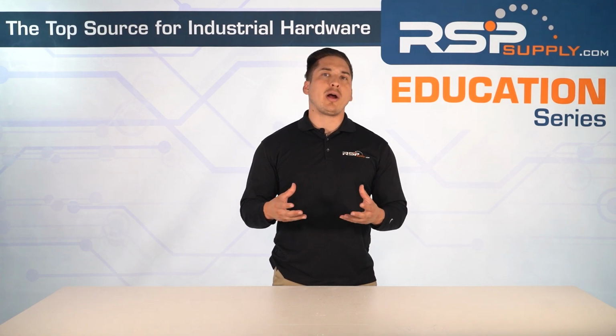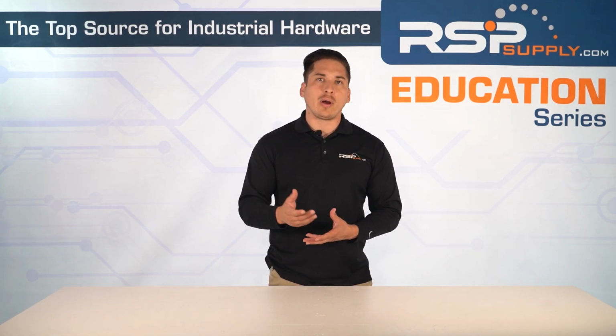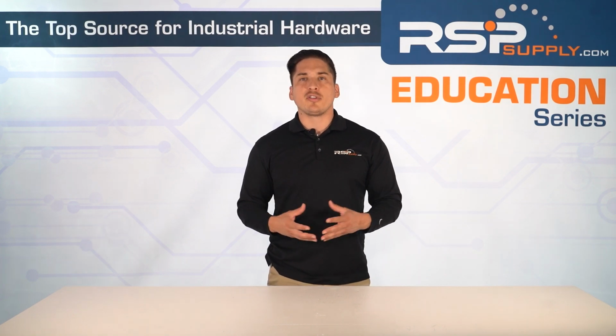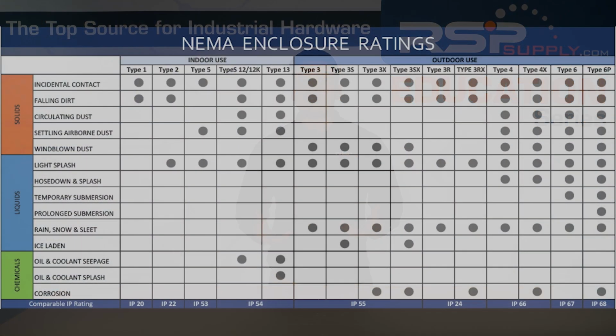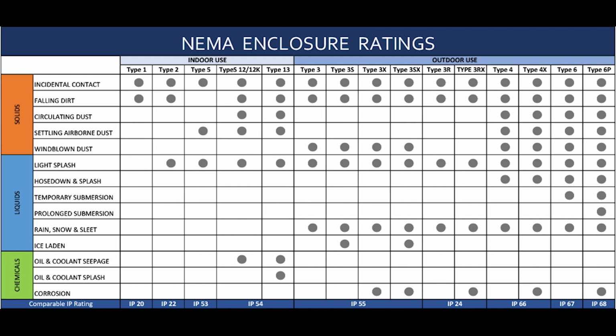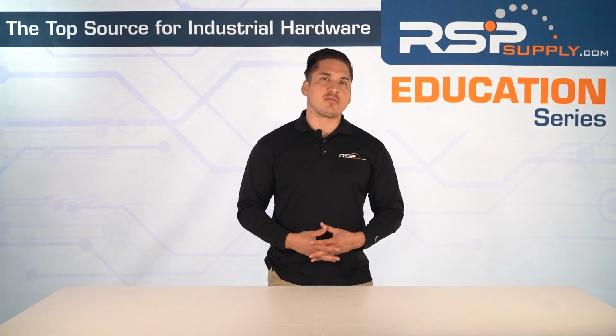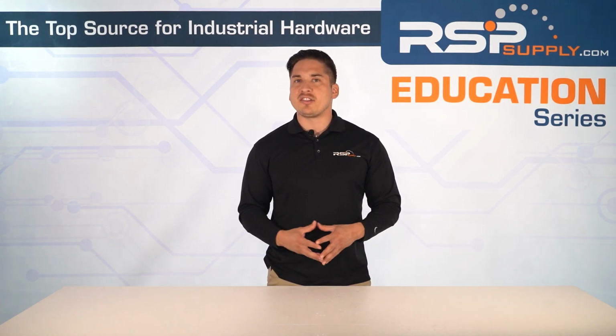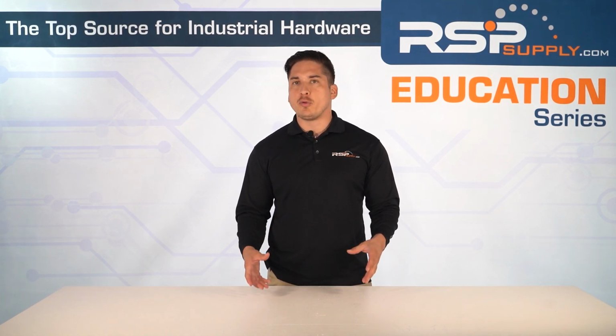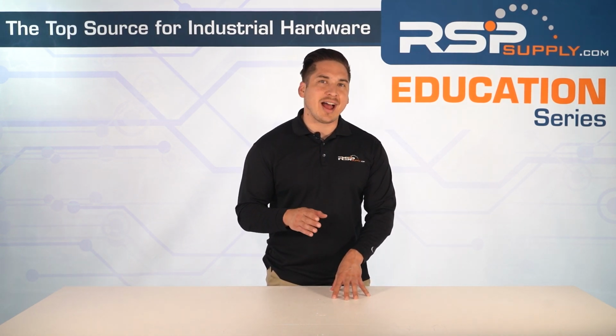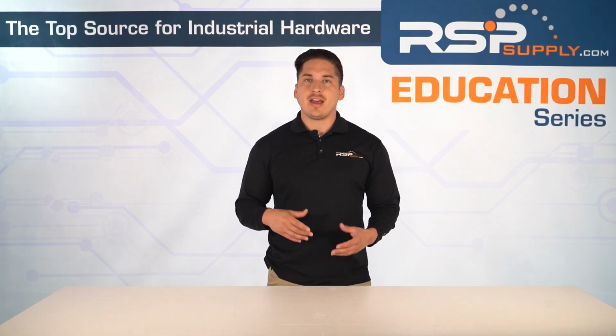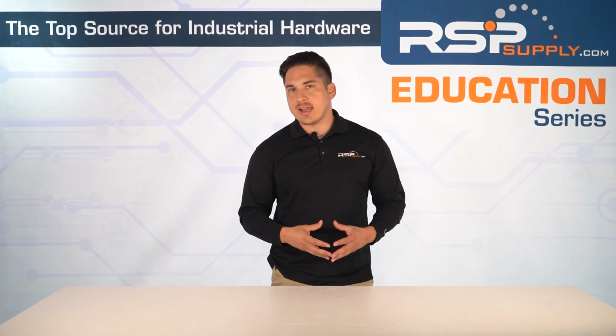Things to keep in mind around environmental conditions, like whether you're indoor or outdoor or around hazardous areas. Indoor versus outdoor, that changes the box you need. If your switch is going inside a building, a NEMA 1 or 12 enclosure might just work fine. But if it's going to be outside, go with NEMA 3R, NEMA 4, or even 4X. In corrosive places like near salt water or certain chemicals, go with stainless steel or fiberglass for extra protection. Think about water, dust, and chemical exposure. If the switch is going in a place where it might get sprayed down or exposed to nasty chemicals, like in food plants or factories, make sure it's rated at least IP66 or NEMA 4X. These ratings mean it'll stand up to water jets and chemical splashes.